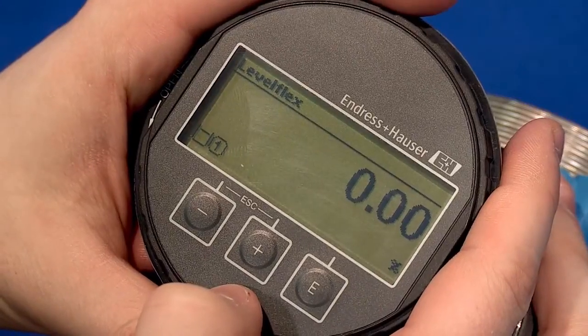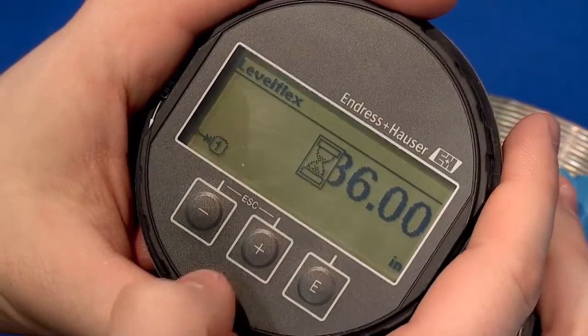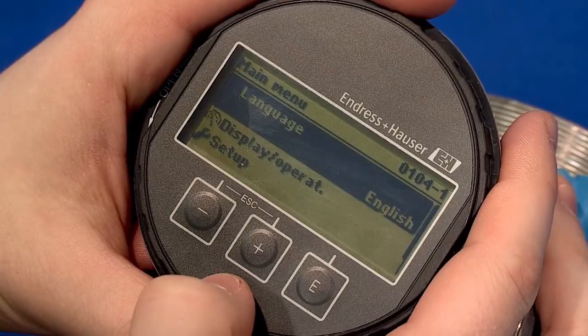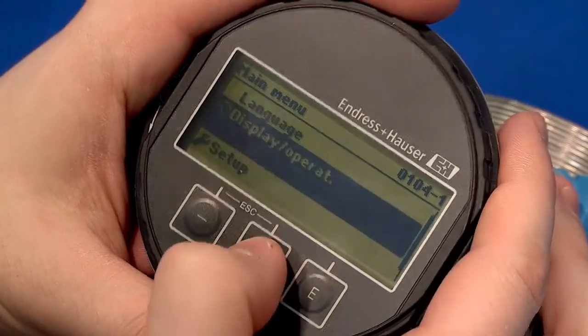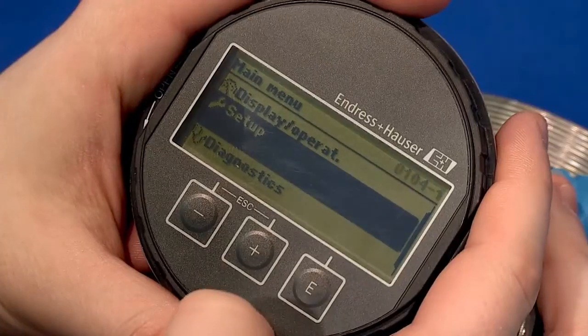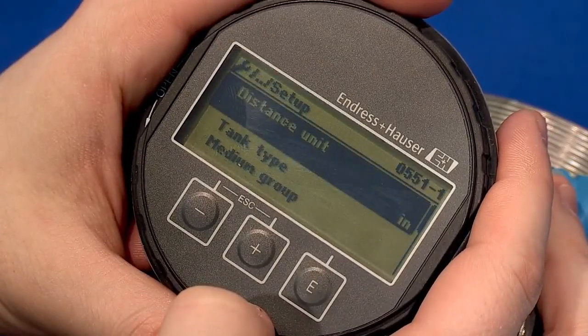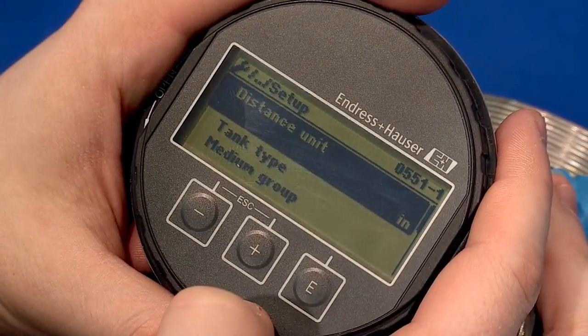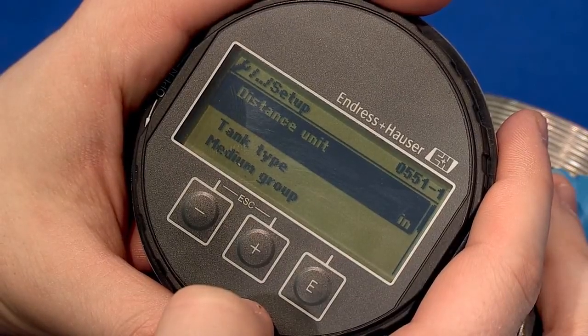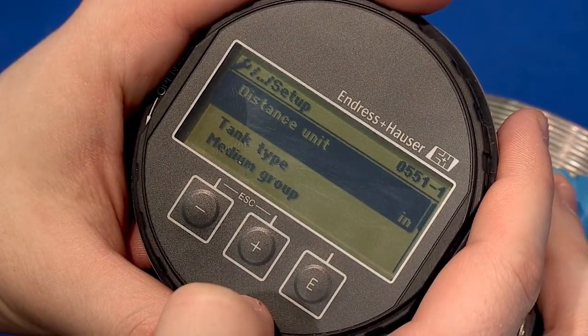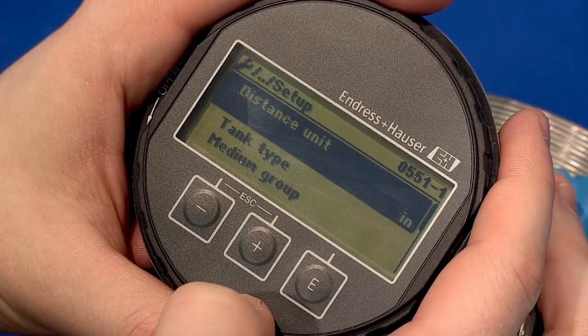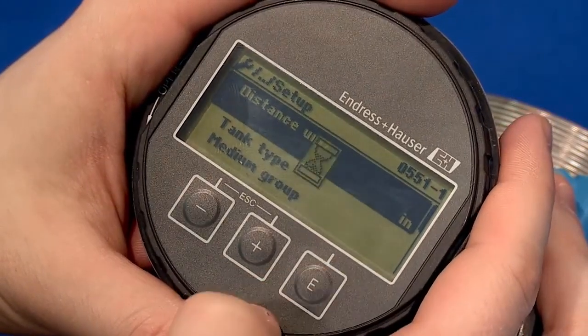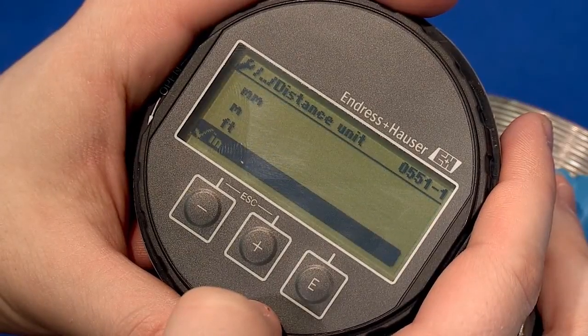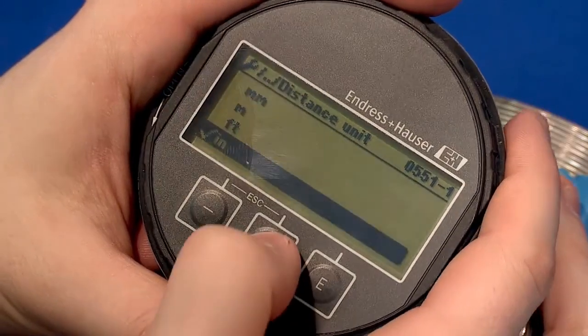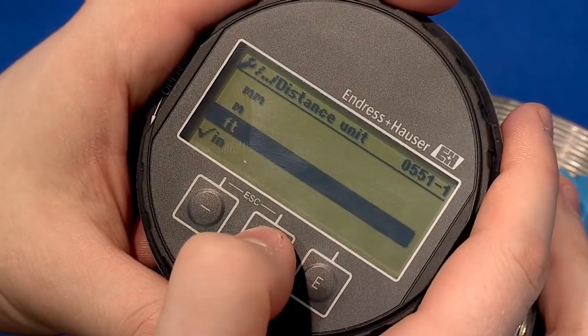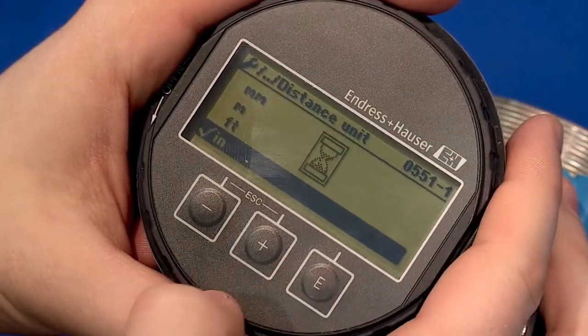To begin the basic setup, we will press Enter to enter into the main menu. Use the plus or minus key to highlight Setup and hit Enter to enter that menu. Once you are in the Setup menu, you will begin selecting the parameters to set your instrument up for a level measurement. The first option is your distance unit. You will press the Enter button to go into the parameter, followed by the plus or minus keys to highlight your choice. Once your choice is highlighted, you will then press Enter to confirm.